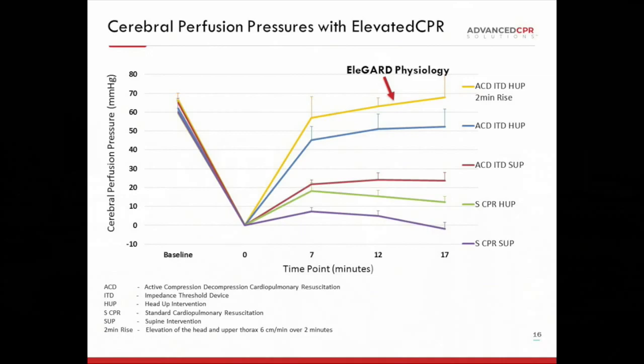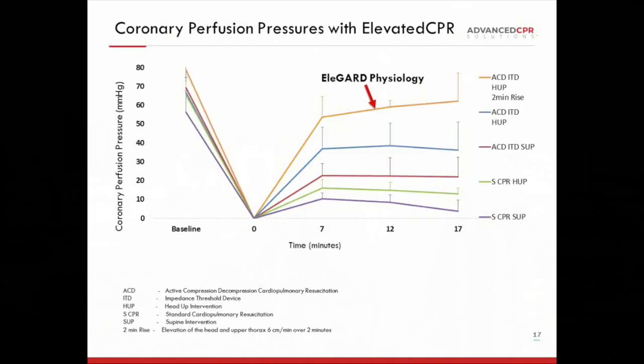Over the last several years, we've developed a unique way to do this which almost normalizes cerebral perfusion pressure over time. The bottom graph in purple shows standard CPR — elevation flat doesn't do very much. ACD-ITD supine is good, and we can make it better by elevating the heart and the head. Using the EleGARD, which is uniquely designed for head-up CPR, we initially place the head and heart in a slightly elevated position, prime for two minutes, and then elevate the head slowly over two minutes to the optimal height. The EleGARD physiology shows cerebral perfusion pressure approaching much higher levels than achievable with CPR in a flat position. Similarly, coronary perfusion pressure — blood flow to the heart — is shown here, and the EleGARD physiology is far superior.